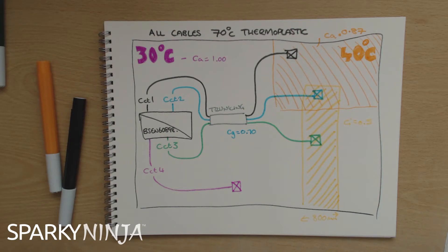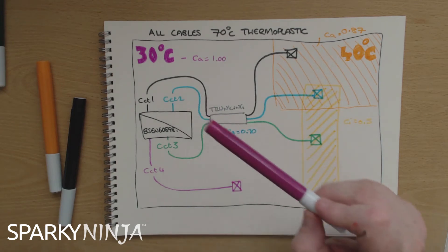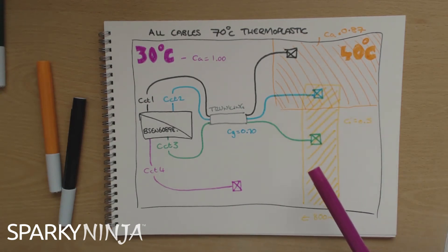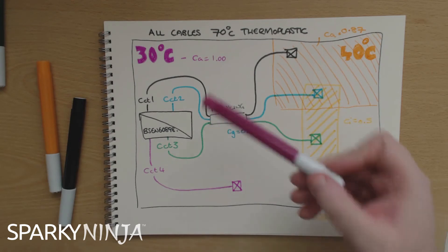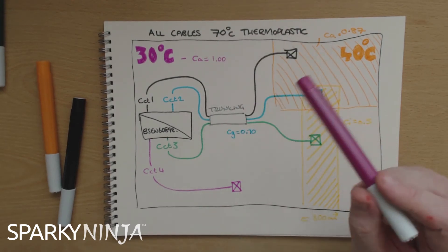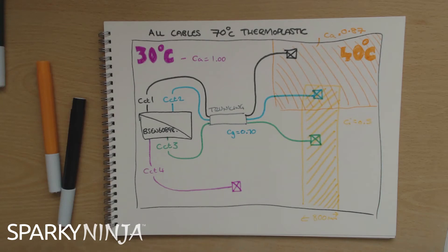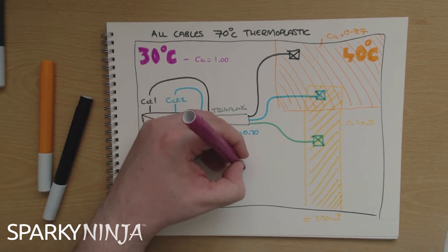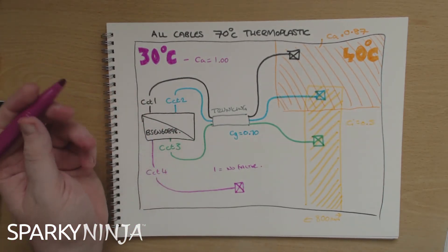We've got these different factors for different reasons, but what I want to cover is what do we do with them for each individual circuit. For circuit one, do I apply factors of 1, 0.7, and 0.87? For circuit two, 1, 0.7, 0.87, and 0.5? For circuit three, 1, 0.7, and 0.5? For circuit four, just 1? If I do that, I'm going to waste my design. Circuit four is straightforward — one factor of 1, meaning no effect, so Iz equals In.